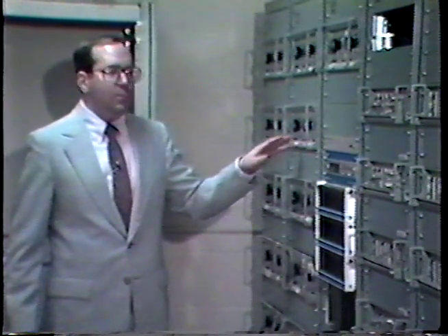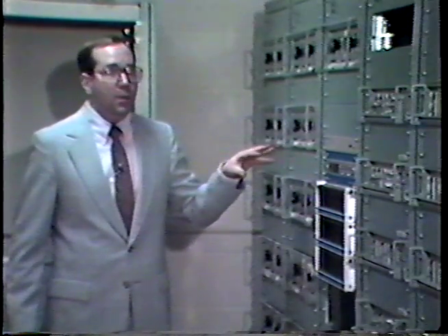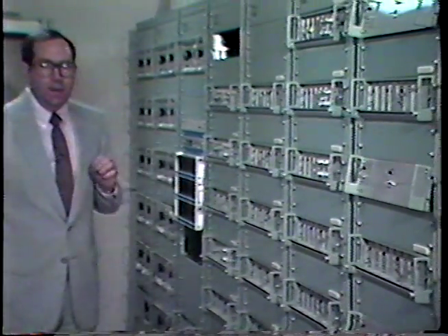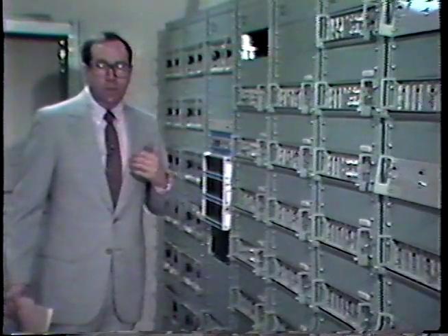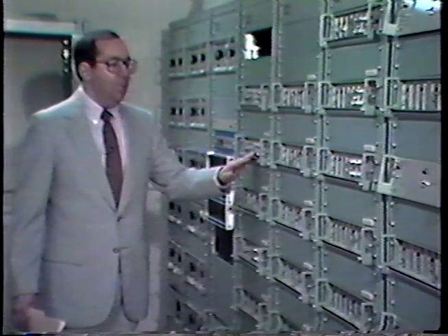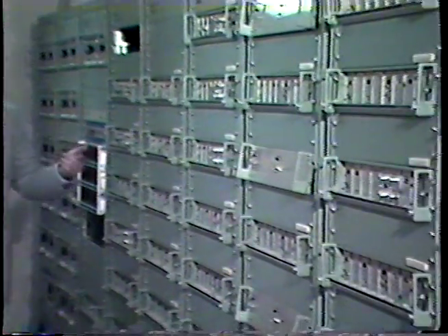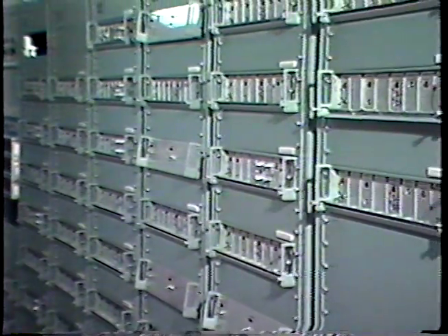And then what happens once we have this microwave signal received and processed from microwave into video and audio, then we have to assign a channel to it for the cable system. And that particular channel that we choose to assign it is created by the modulators. For example, we take the movie channel and take its video and audio and process it on channel 25.